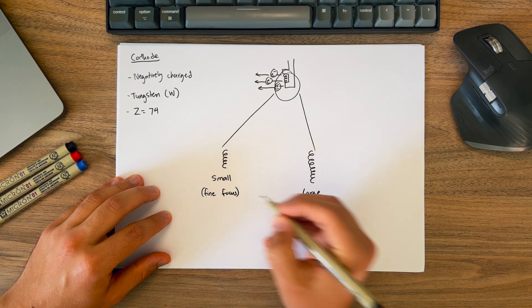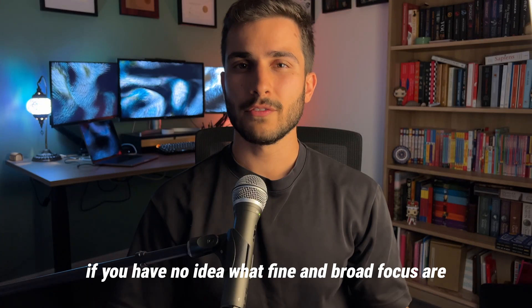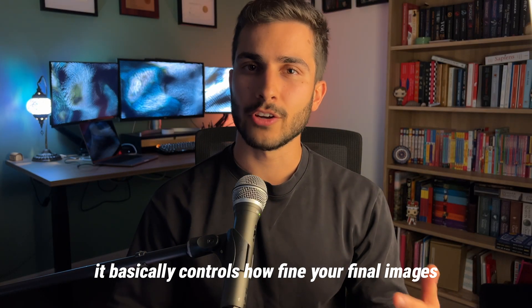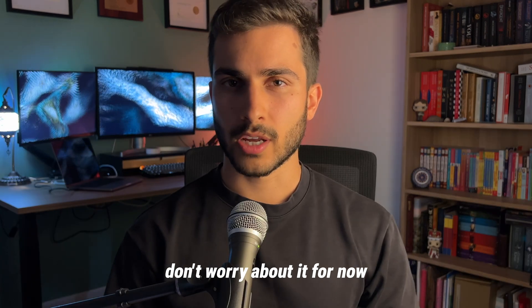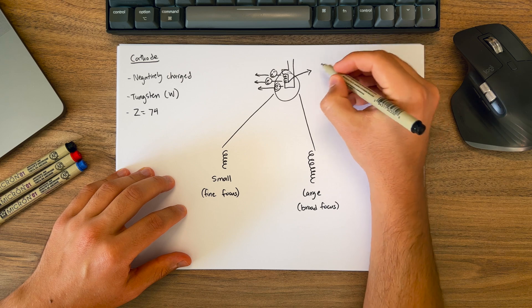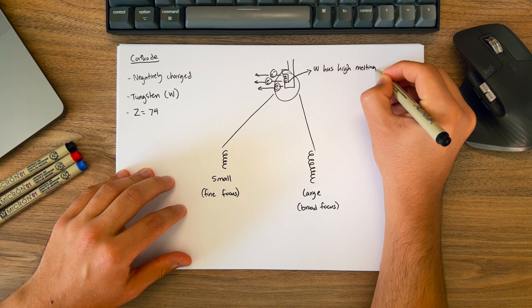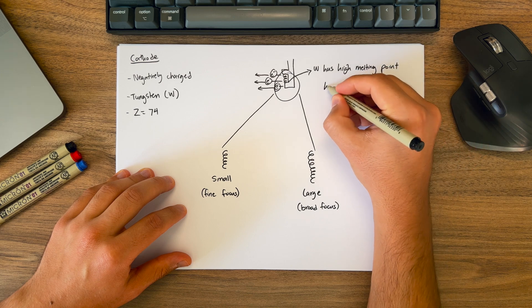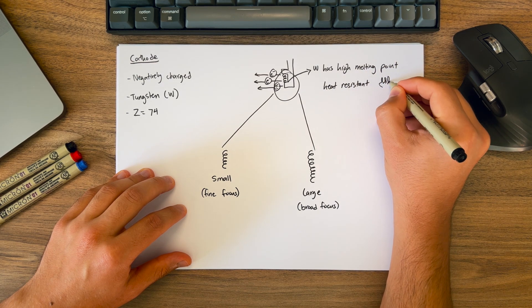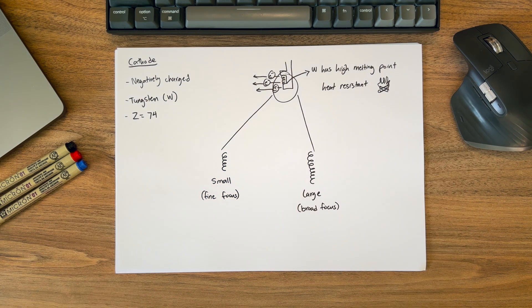The small one is used for the fine focus setting and the large one for the broad focus. If you have no idea what fine and broad focus are, it basically controls how fine your final image is — I'll make another video and link that below once it's ready. The material of the cathode is important because it's able to withstand the thermal stress of repeated heating cycles without significant evaporation or deformation of the filament, because it's strong enough to maintain its shape and size during x-ray production, which can get quite heated.